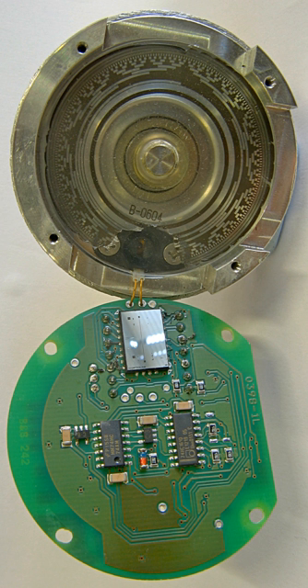Topic: Encoder technologies. Conductive: a series of circumferential copper tracks etched onto a PCB is used to encode the information. Contact brushes sense the conductive areas. This form of encoder is now rarely seen except as a user input in digital multimeters. Optical: this uses a light shining onto a photodiode through slits in a metal or glass disc. Reflective versions also exist. This is one of the most common technologies. Optical encoders are very sensitive to dust.